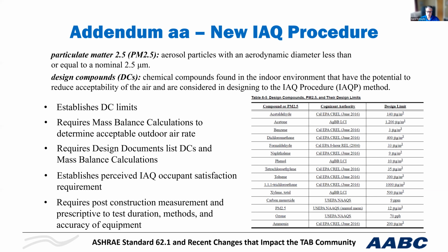So if an engineer is using this method, he better ensure that he doesn't undersize the system and can't go backwards, because if for some reason he fails the test more than once and wants to increase the outside air, but the ductwork was sized for less air or the equipment was sized for less air, it's going to be a challenge going backwards. So something to consider. It's an important thing.